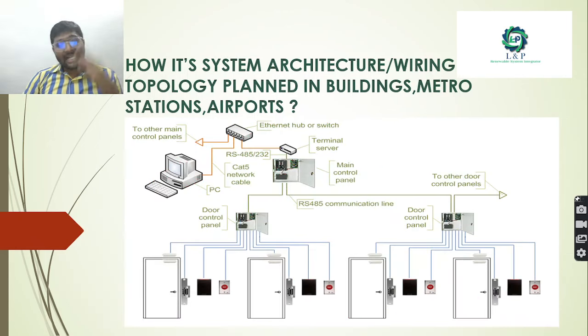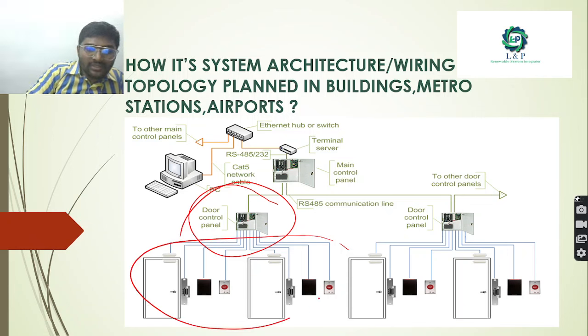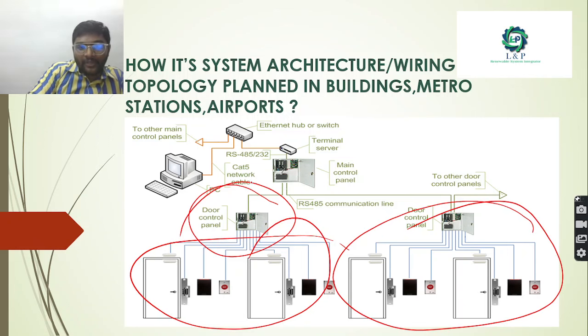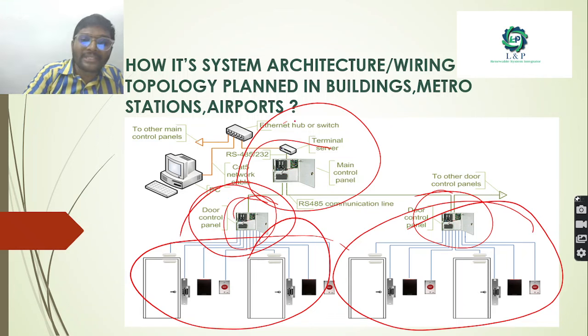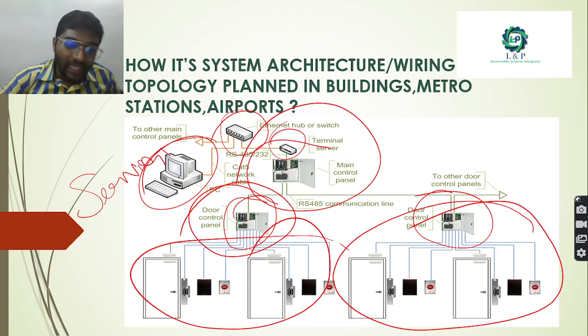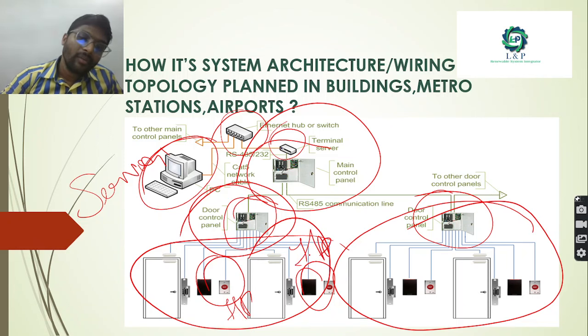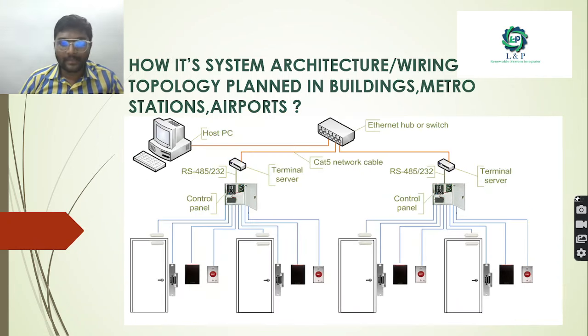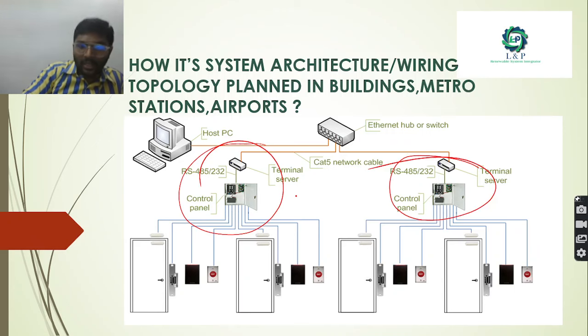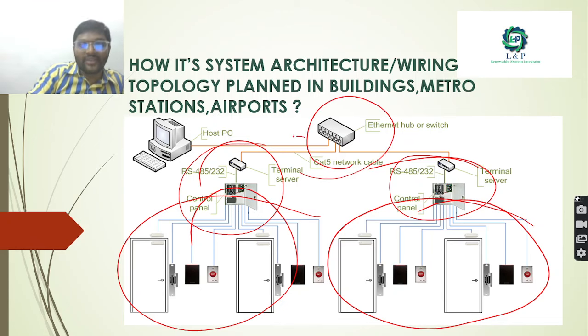In another method, connect all door wirings through the RS-485 communication line from card readers to a single main control panel. The card readers act as inputs and the relay-commanded outputs go to the locks. Connect via Ethernet switches or terminal servers to the PC or server where all details are stored and reports are generated. For multi-story buildings, have a door control panel for two rooms, connect those via RS-485 to the main control panel, and from the main control panel connect through Ethernet hub to the server. Alternatively, control two rooms from a door control panel and connect directly through the Ethernet switch to the server.